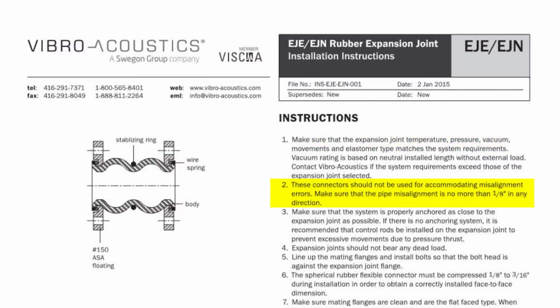Next, while these expansion joints can accommodate offsets, they should not be used to correct misalignments. We'll want to make sure the connected pipes are aligned within about 1/8 of an inch. It's important that the expansion joint not bear too much stress. The pipe system should be anchored nearby to control pressure thrust caused by pump startup or shutdown. Control rods should be used if the pipe isn't anchored.